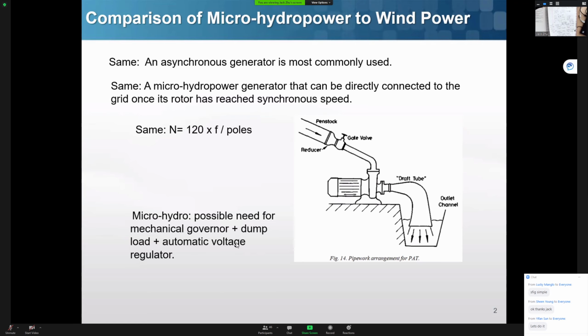So sometimes you don't have a good mechanical governor to be able to supply the actual power to push, because with micro hydro, you don't have those very complex controls of a utility hydro generator, right? So what they usually do is they will have almost like a fixed speed rotation down there to generate the maximum power.